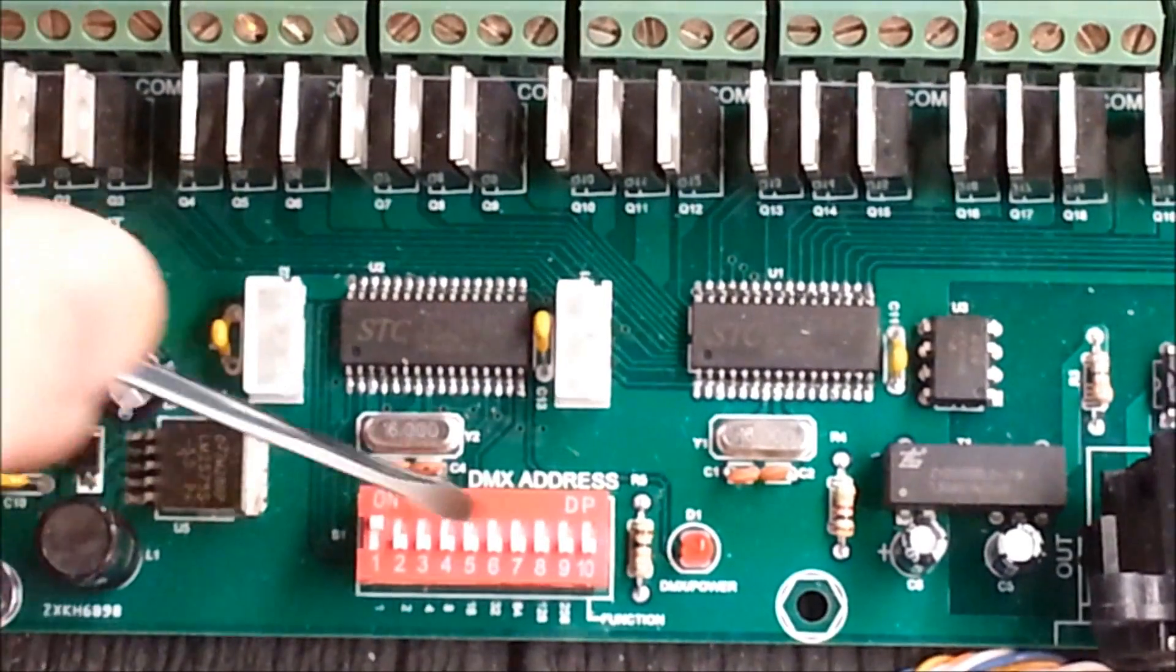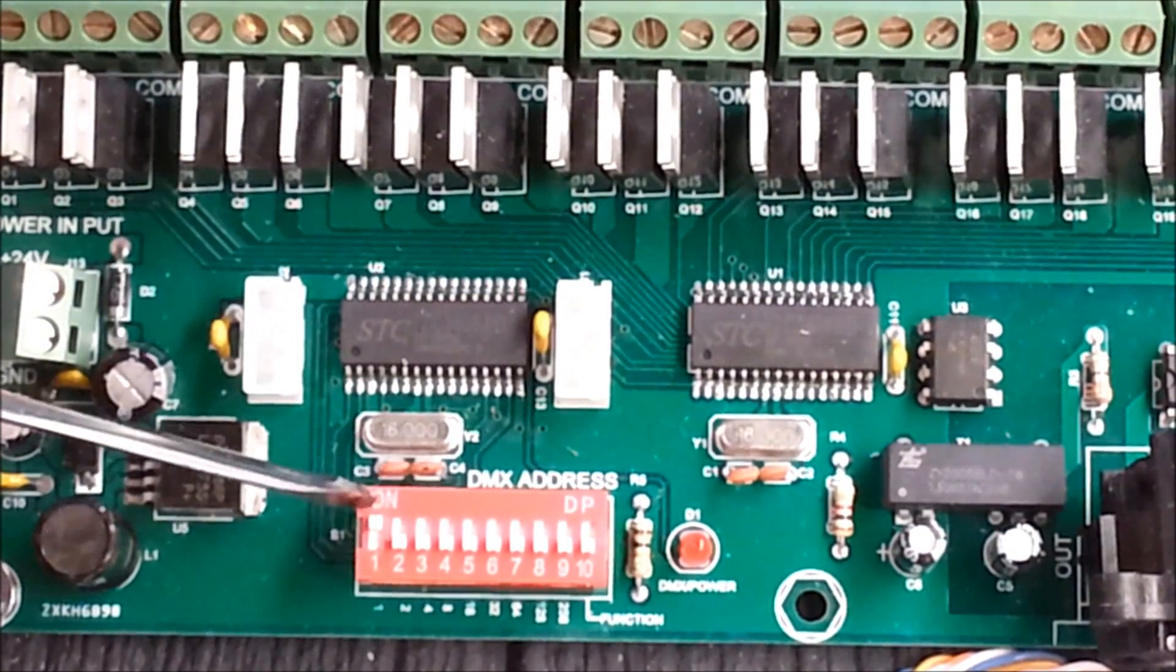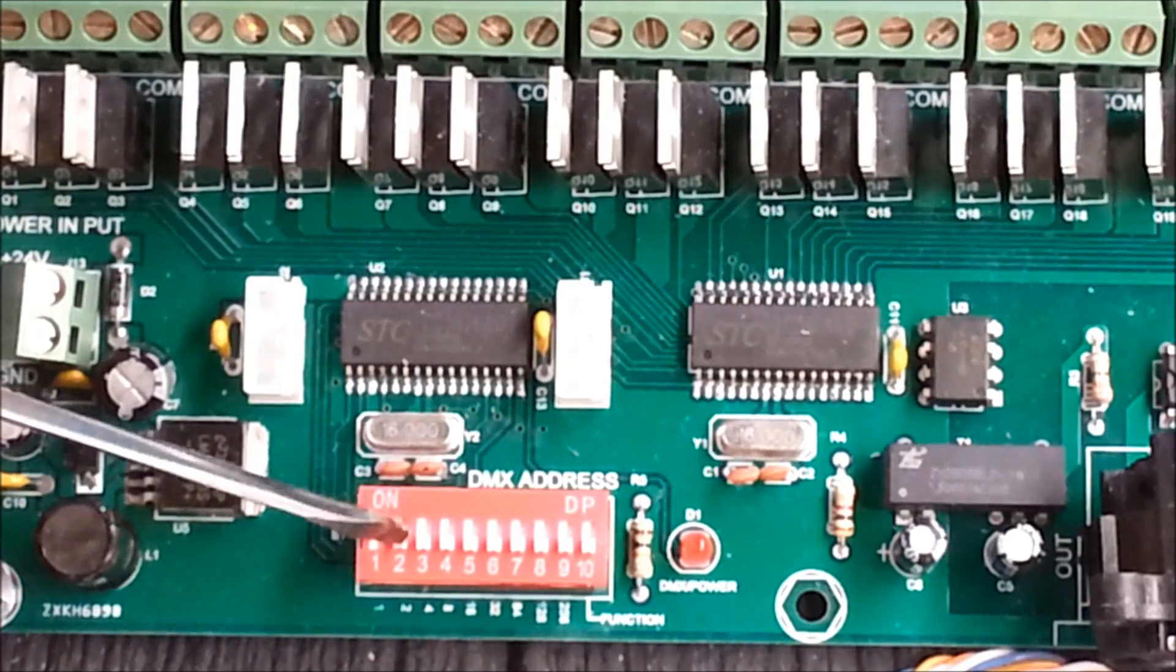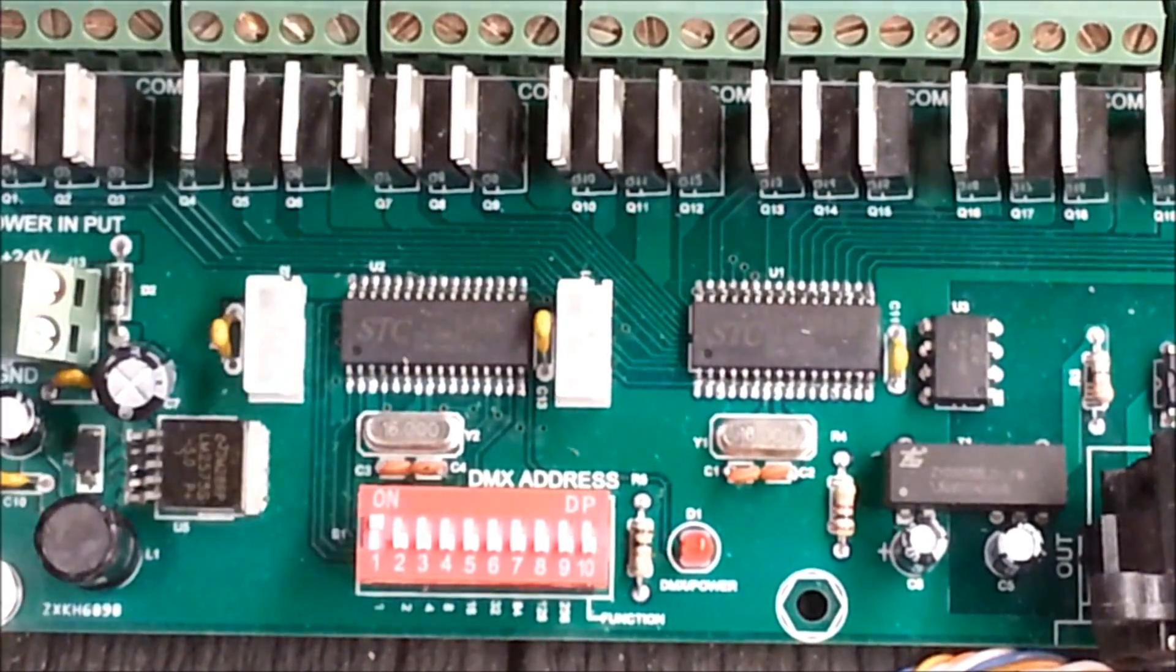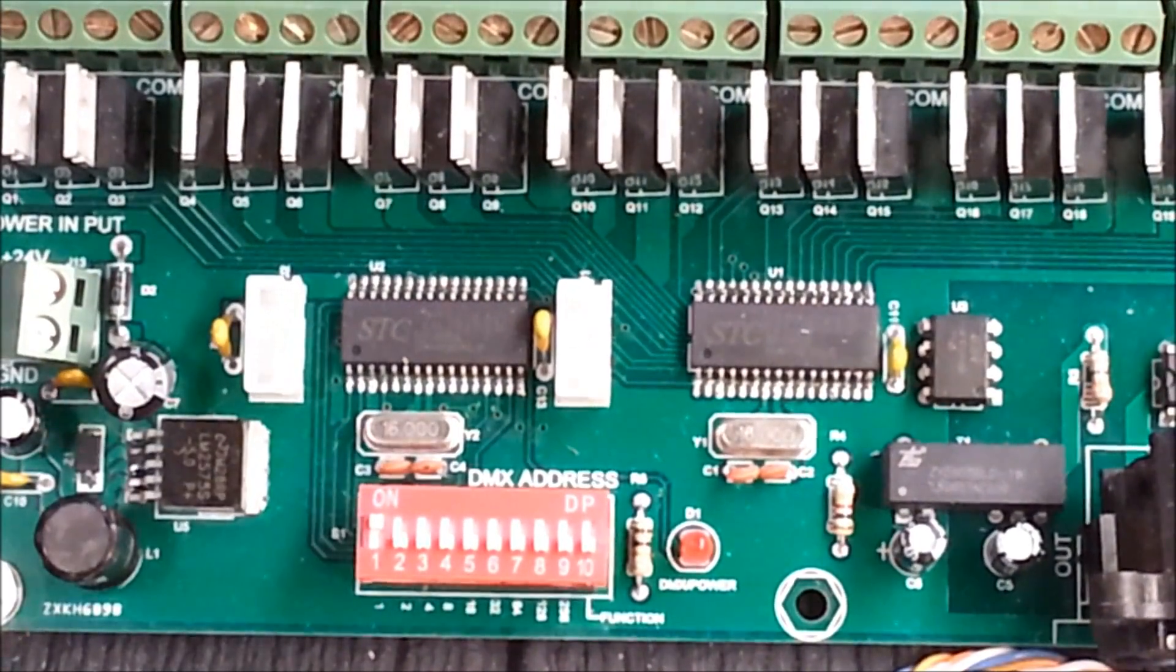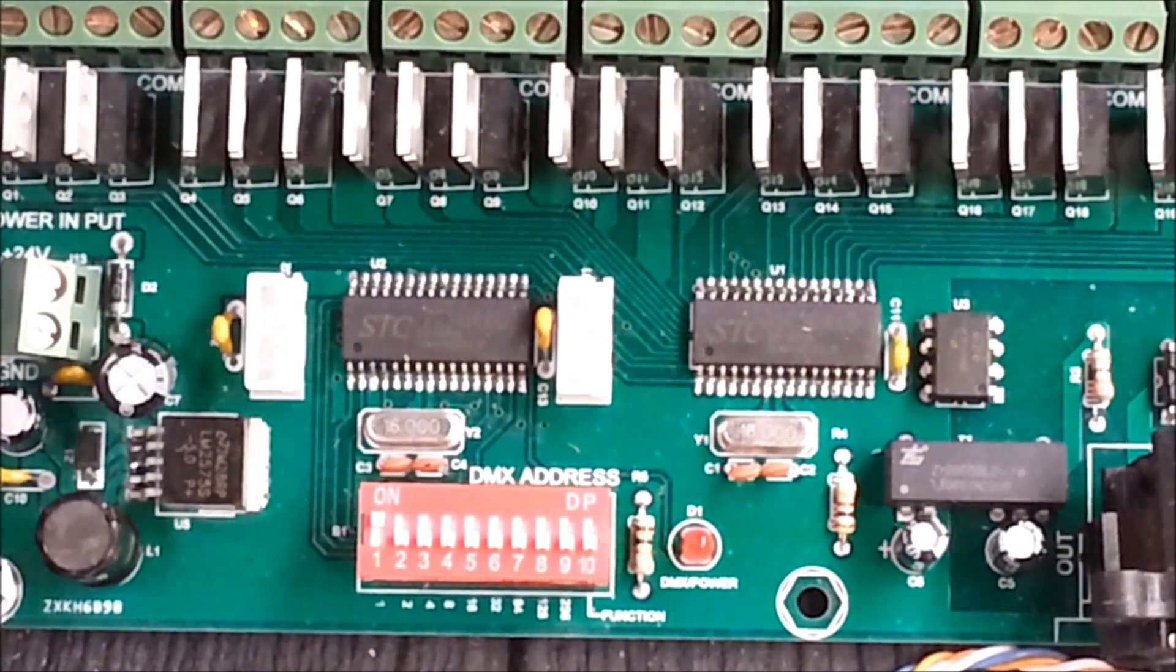All of the other dip switches, whenever they're in the opposite position, are off. Now you have to pay attention to your dip switch setting, because some of them, the on is on the bottom and the off is on the top, but it will denote to you which is the correct position for the dip switch. So this controller here is now set up to be our controller number one and channel number one through channel number 27, up here on the outputs.